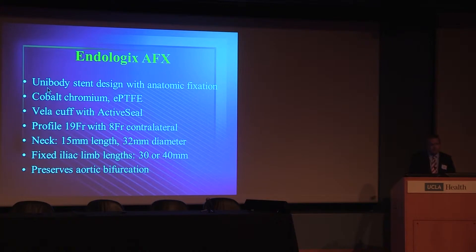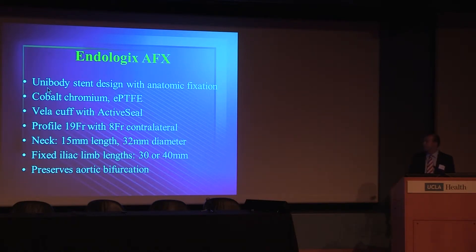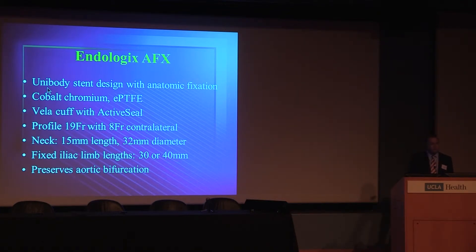Endologix is a very different design — a unibody design that sits on the aortic bifurcation, providing so-called anatomic fixation with columnar support. It has a cobalt chromium stent frame loosely bound to PTFE material. Their proprietary Vela cuff material expands to create an active seal. The profile is a 19 French OD or 17 French ID with a very small 8 French contralateral limb. It can treat 32 mm diameter necks with 15 mm length. Iliac limbs are fixed at either 30 or 40 millimeters, which can be an advantage or detraction. Sitting on the aortic bifurcation also allows for later infrainguinal intervention.